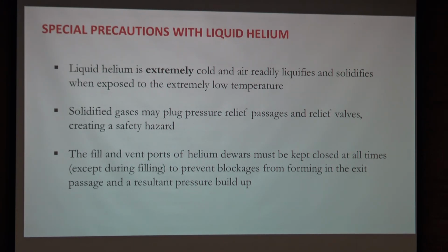Essentially anything that is in the pipes that are supposed to provide a way for your cold gas to escape, whether it's water or even possibly carbon dioxide, may start to freeze and build blockages. So with such containers, be extremely careful to make sure that the pressure reliefs don't get frozen up.